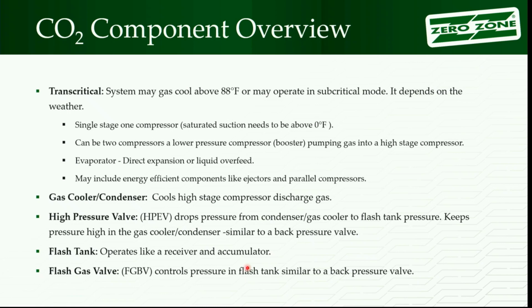So when we do the sizing on it, the first thing we look at is how big a receiver you need for the charge of the system, the size of the system. Then we confirm that the velocity is slow enough, that the tank's big enough in diameter that we're not going to suck out drops of liquid with it over to the compressor. Out of that system, then we have the flash gas bypass valve. The flash gas bypass valve holds a pressure in that tank, and it's a back pressure regulating valve. Another term, inlet pressure regulating valve. It's going to keep that tank pressure higher. Because the gas from the flash tank goes over to the high stage compressor. If I don't have something in the middle to build up pressure in that receiver, I'm going to have a problem with my evaporator.